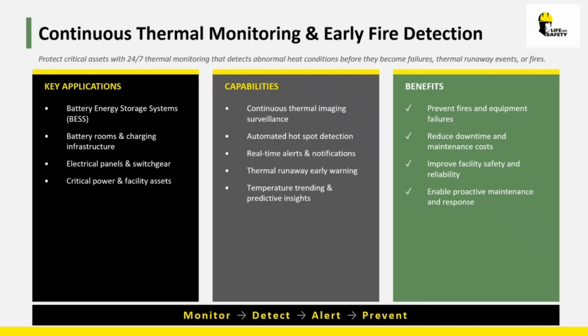Currently, several of my customers doing this are doing thermal imaging and IR scanning as a cassette or module moves from one station to the next, just to double check it. One of my other customers, an EV manufacturer, receives fully constructed EV batteries from an outside supplier. They scan it before it even comes into the plant, then once it goes into the vehicle and gets connected, it gets scanned one more time before it goes out the door. Those are constant checks—one of your best tools for spotting a problem is that infrared scanner.